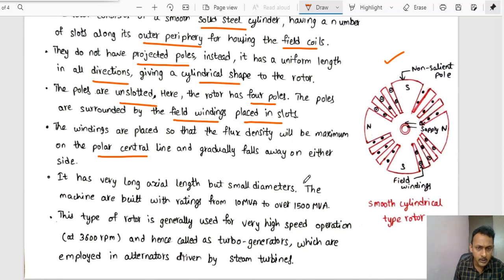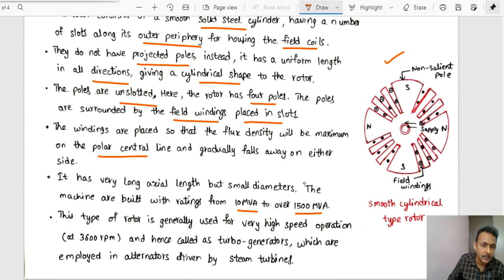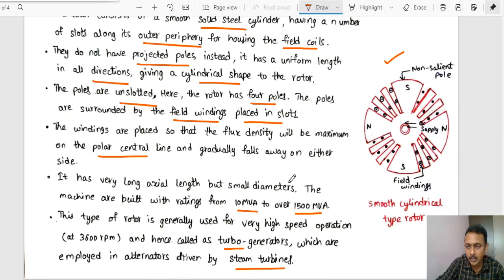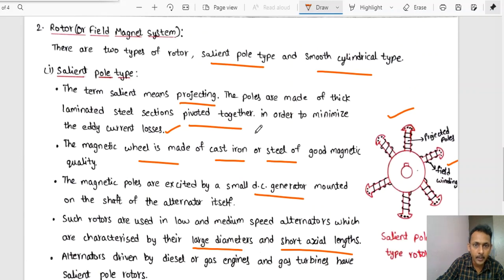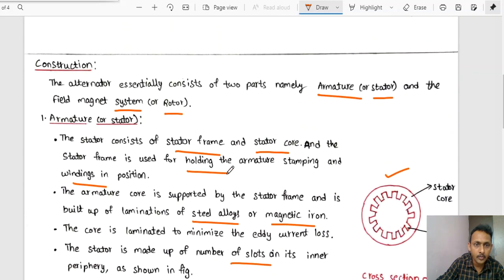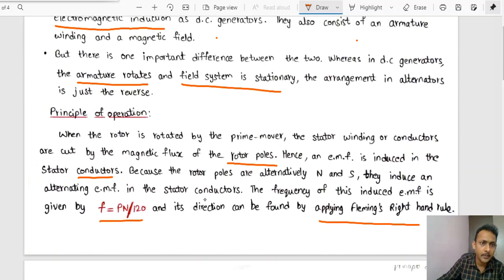The smooth cylindrical rotor has a very long axial length but smaller diameter. Machines built with ratings from 10 MVA to over 1500 MVA use this type of rotor. It is used for very high-speed operations at 3600 RPM, and is also called turbo generators, employed in alternators driven by steam turbines. The frequency of the induced EMF is given by f = PN/120.